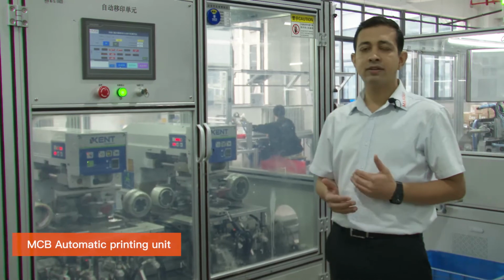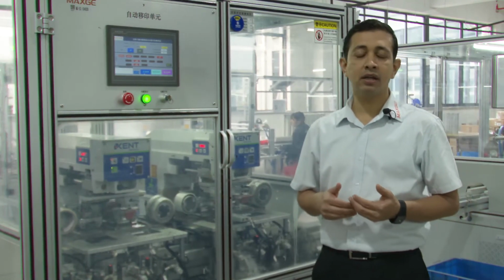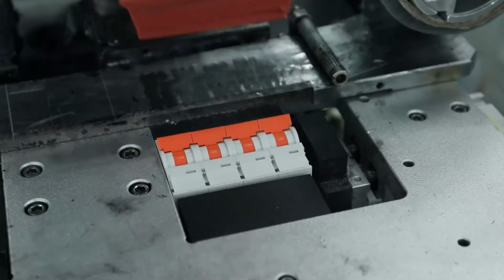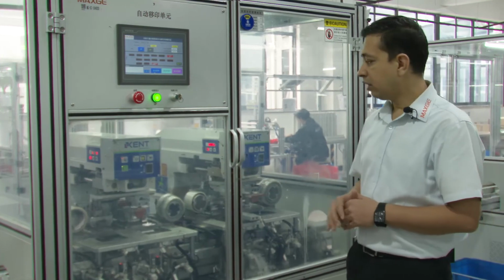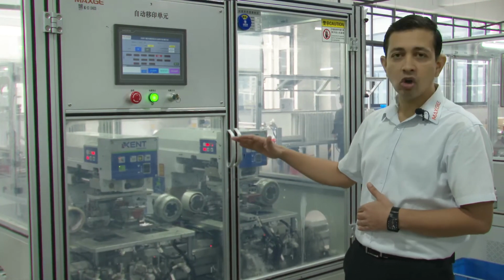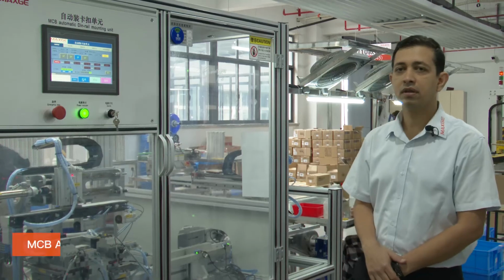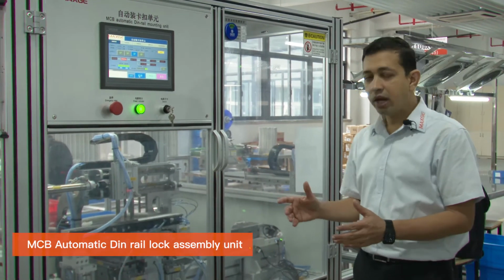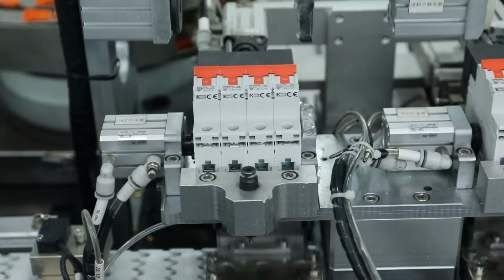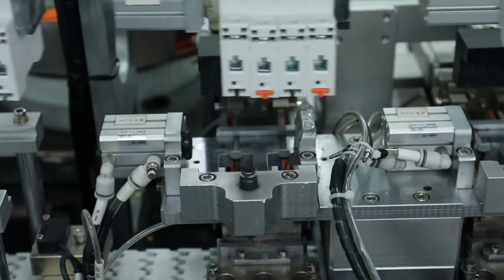After we have done the whole series of tests: first the barcode printing, then the single pole riveting, then the magnetic thermal calibration, thermal verification, then the magnetic testing on the single pole, then the multipole coupling, multipole riveting, and then the multipole again tested for magnetic. All the series of tests has been done. Then finally the MCB comes for printing. Here this machine does automatic pad printing on the top face of the MCB. This is the final station, wherein the DIN clips are inserted automatically. This is the automatic DIN clip insertion station.